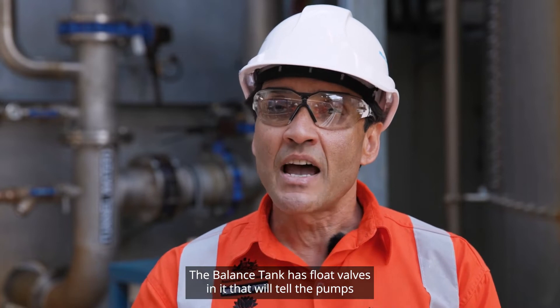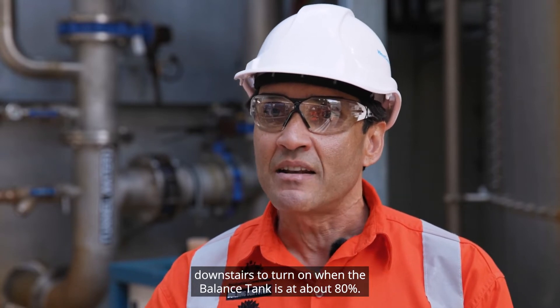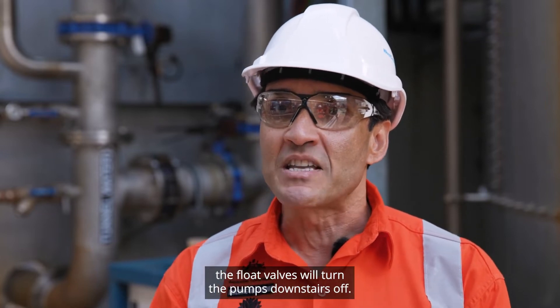The balance tank has float valves in it that will tell the pumps downstairs to turn on when the balance tank is at about 80%. When the balance tank fills to approximately 90%, the float valves will turn the pumps downstairs off.